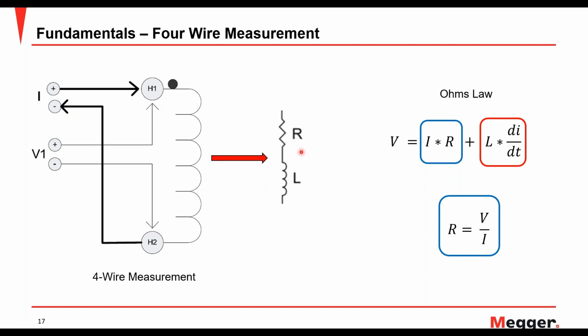The reason being, your winding is made up of some resistive component and your inductance component. Basically, winding is wound around a core, and that's what generates inductive component in the winding. So I don't want to care about the L di by dt. That's your basically inductor part of it. I don't want that. So what I do is I just care about my resistive components. So I want to negate this part. So what I do is use DC. DC only measures resistance. It does not measure inductance or capacitance. So that's why I'm using DC in a transformer in order to account for only resistance measurement in a winding.